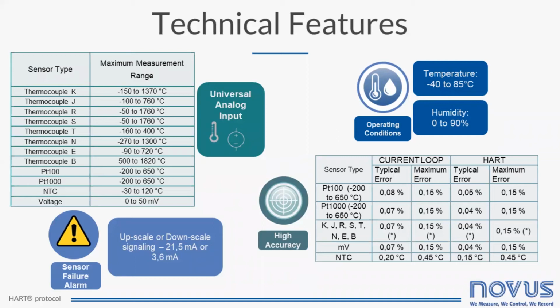NOVUS transmitters, TX ISO Rail HART and TX ISO Block HART, are NAMUR and NE43 compliant. The sensor failure alarm establishes the output current behavior when the transmitter indicates a failure. Downscale: output current goes to lower than 3.6 milliamps, typically used for refrigeration. And upscale: output current goes to greater than 21.5 milliamps, typically used for heating.